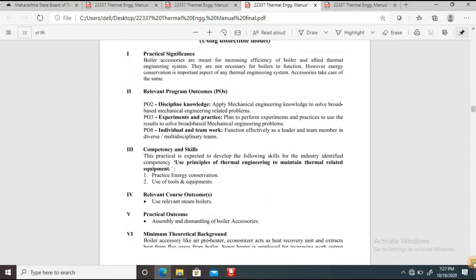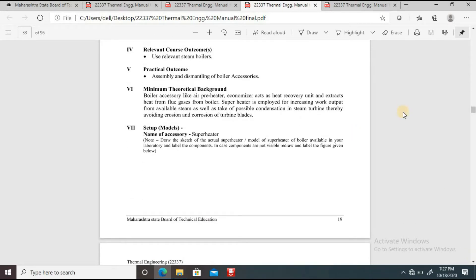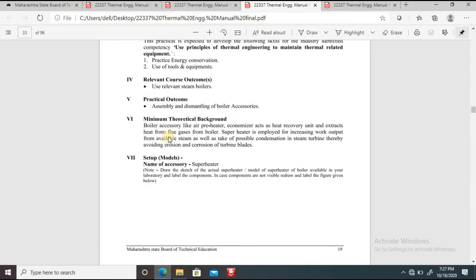Now let's see what are the boiler accessories. The minimal theoretical background: boiler accessories like air preheater and economizer act as heat recovery units and they extract heat from flue gases. The superheater is employed for increasing work output from available steam as well as to avoid possible condensation in the steam turbine, thereby avoiding erosion and corrosion of turbine blades. The construction and working of air preheater, economizer, and superheater will all be discussed in this practical.